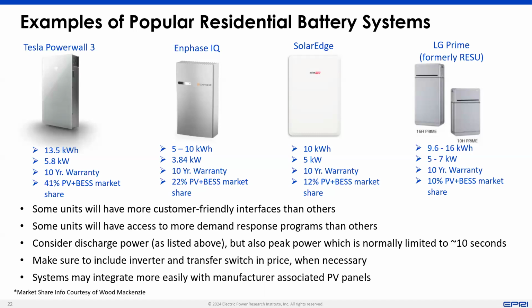You can say the same for many of these other systems, but Tesla has probably done a superior job in that respect. You want to consider not just the discharge power, 5.8 kilowatts for the Powerwall or 3.84 for the Enphase, but also the peak amounts they can discharge for very short periods of time. If your AC comes on and you have a large power demand quickly, some of these batteries allow a peak power discharge to match that. Sometimes one battery can do that depending on the size of the AC system, sometimes you need two batteries to start up an AC system on battery alone if the grid is down.